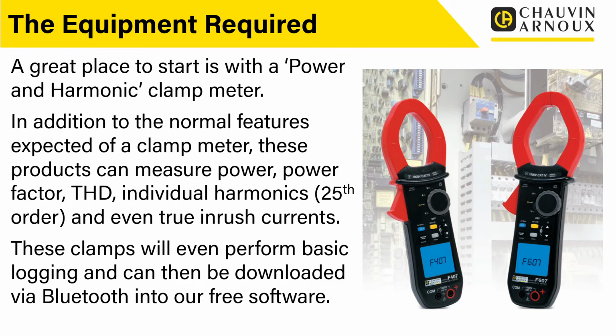But a lot of so-called inrush meters are basically looking for zero current, and then you turn it on, it measures all of the current, and that's it, that's your inrush. But it's looking for a starting point from zero, which is no good if you've got a circuit where you've got other things connected on the circuit. You've got a base load, a certain amount of current flowing anyway. You're just looking for the additional inrush because that's the bit that's causing the problem. That's the bit that's causing your breaker to trip or your fuse to blow. These actually will measure true inrush, so they are really useful in that regard as well.